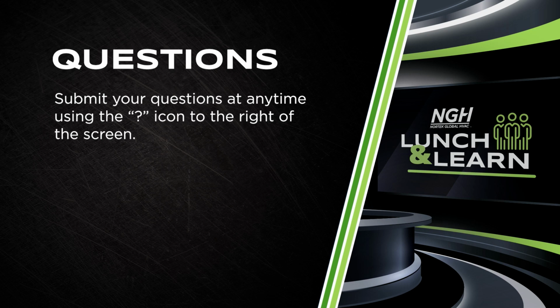There's a question about TXVs - are they going to be rated, any change to where they're located? The A2L rated TXVs will definitely be different because a TXV works with a charge bulb sensing the temperature in the system, and the gas in that charge bulb is specific to the refrigerant it's metering for. So that charge will change when using R454B. You certainly have to use an R454B specific TXV in an R454B system. If you tried to use a 410A one, you wouldn't get the right behavior with the valve opening and closing - same as if you tried an R22 TXV with 410A, or R32, it wouldn't work, same thing, because of the thermodynamic properties.